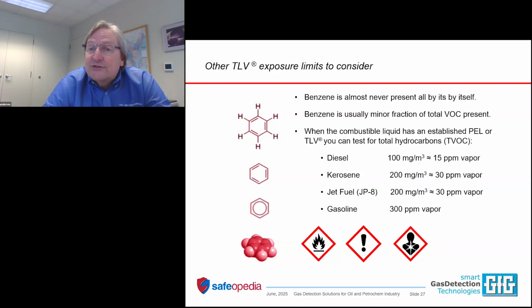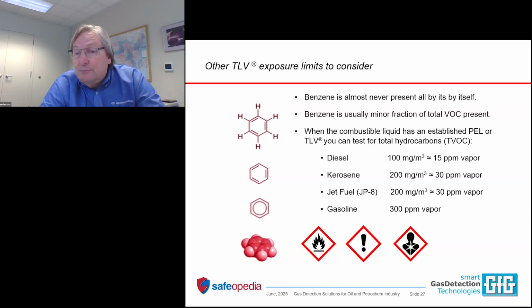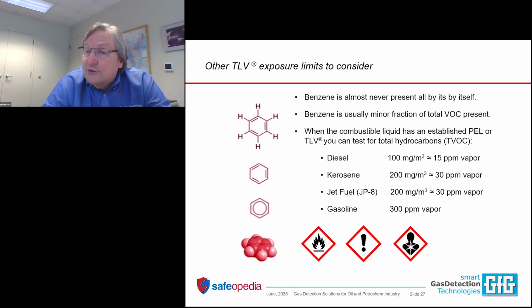When the combustible liquid has an established permissible exposure limit, or TLV, it would be permissible to take action based on TVOC and set your alarm at, say, the diesel TLV limit. The TLV is designed to be protective for all the stuff that's in the diesel vapor, not just the tiny fraction of vapor that is due to the presence of benzene. You have a TLV for diesel, you have a TLV for kerosene, you have a TLV for JP8, jet fuel, you have one for gasoline. It's a lot easier if you're taking action for total VOC at 15 ppm than it is to try to take action for benzene only at 0.02 ppm.